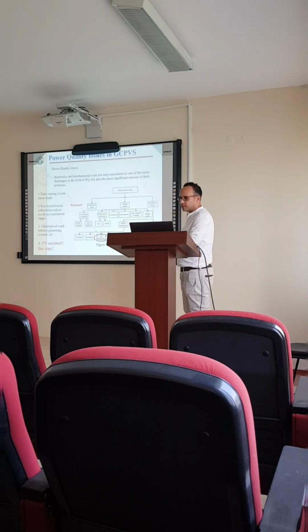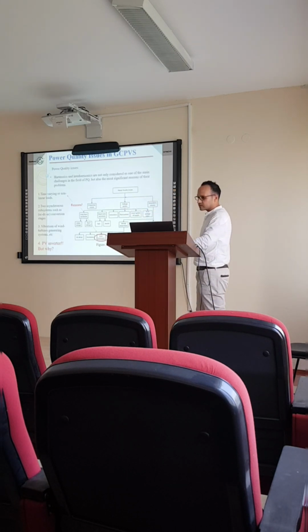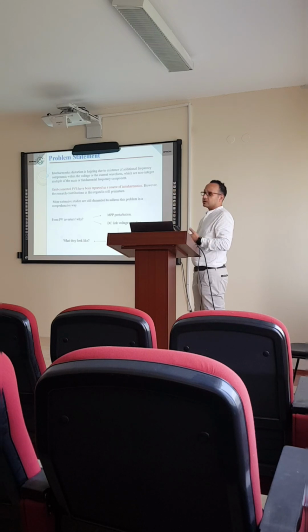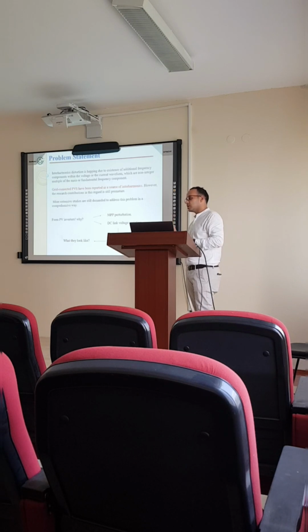Power quality issues are usually classified into 3 parts: frequency events, voltage events, and waveform events. We are working in this thesis on one of the waveform events happening in steady state called interharmonics, defined as a non-integer multiple of the fundamental component in voltage or current. We'll talk about this later, but they are not at 50, 100, or 150 Hz - they're at values like 65 Hz, 66 Hz, which is very challenging for the detection process, as we will explain.